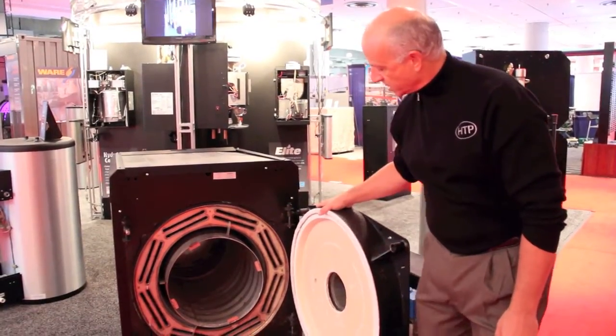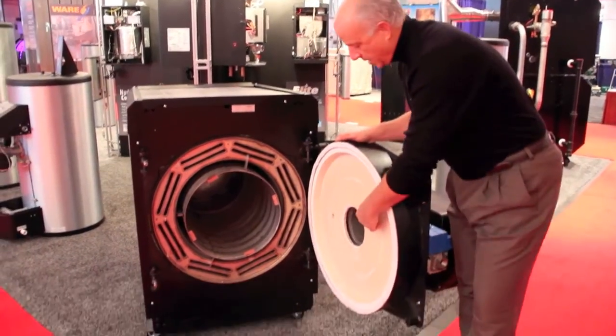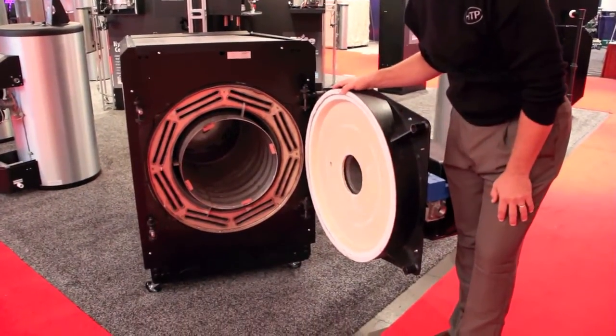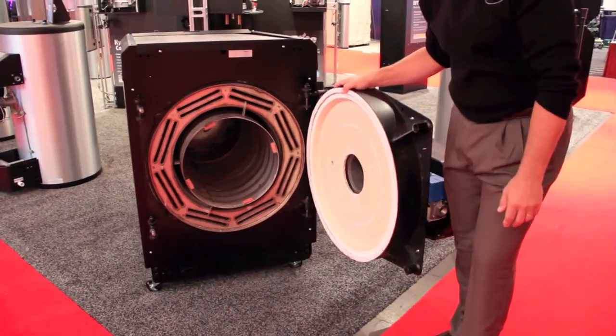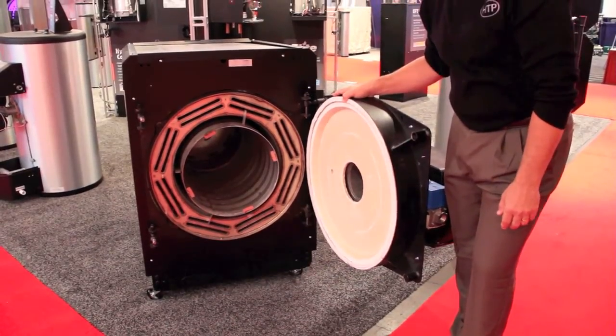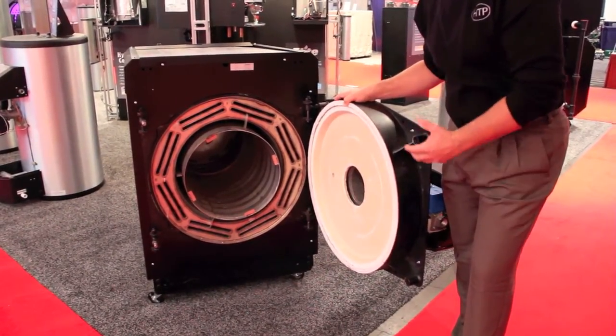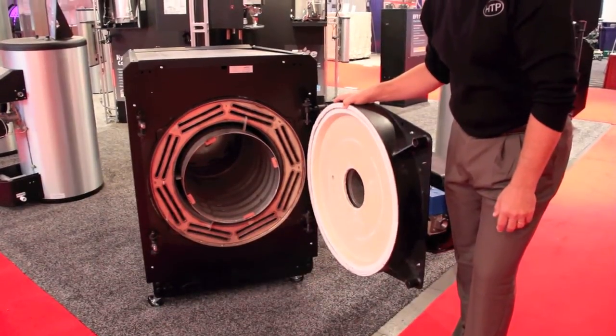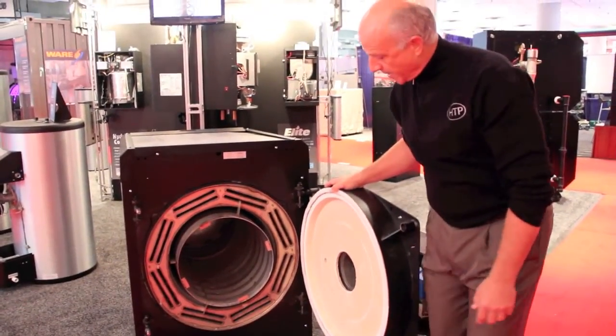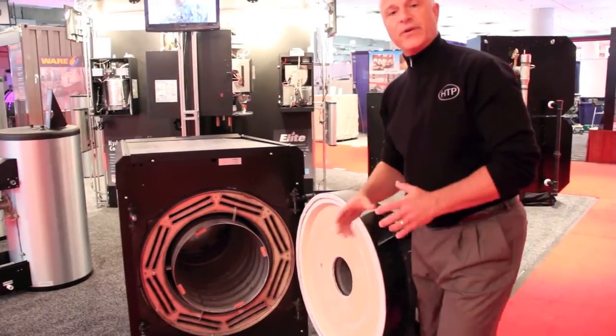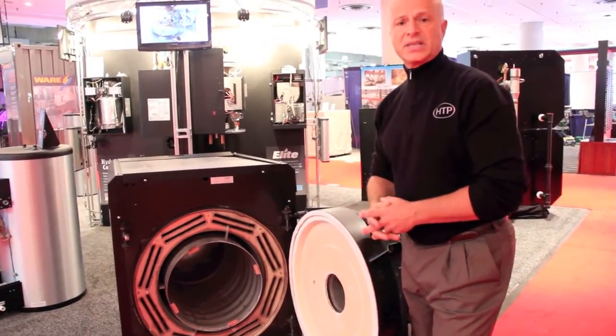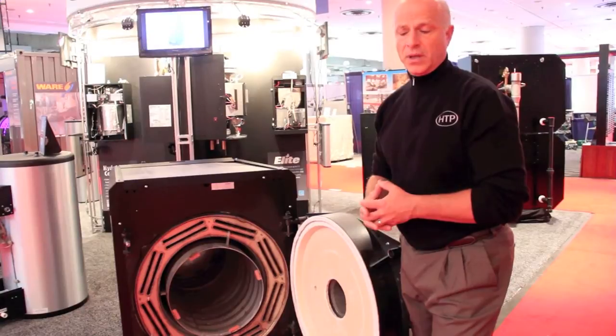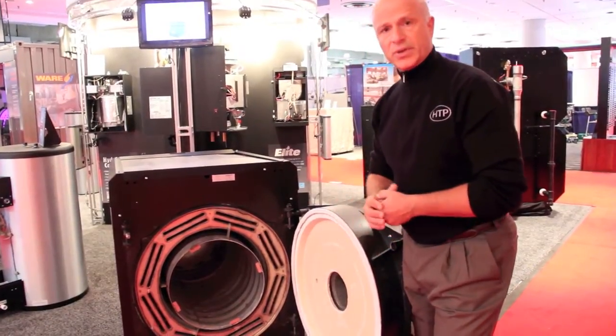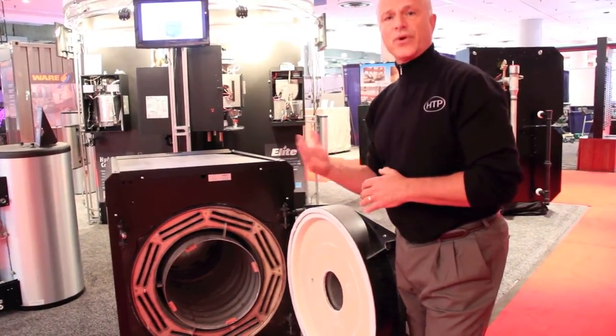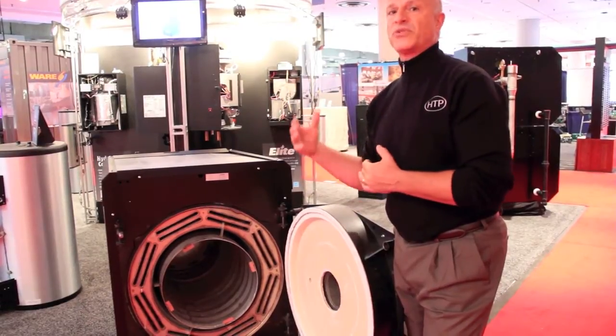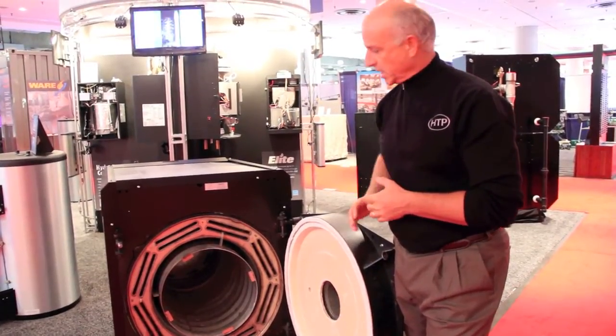Another unique feature of the system is this patented inward firing burner technology. This is a first in the industry, inward firing with the mesh burner. It gives us turndowns up to 15-to-1. It's also very clean burning. Its NOx levels are about 9 ppm. Right now we have a 15-to-1 turndown with this burner, and we're planning to go even further. We've tested it. We can get up to almost 50-to-1 with this burner technology.